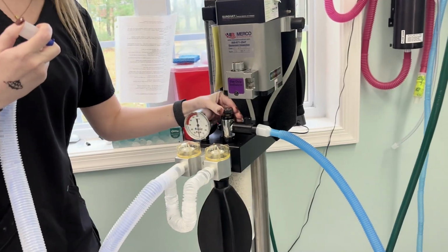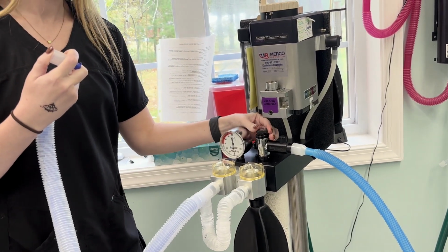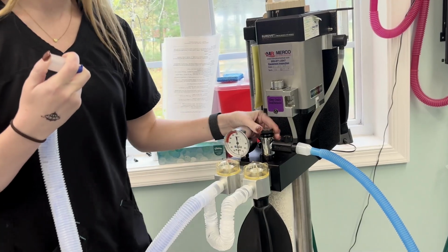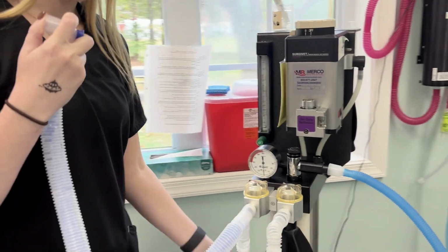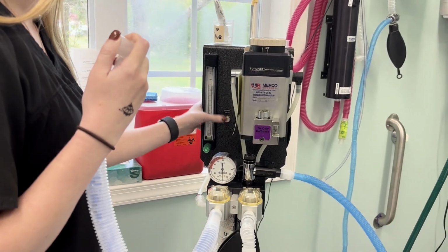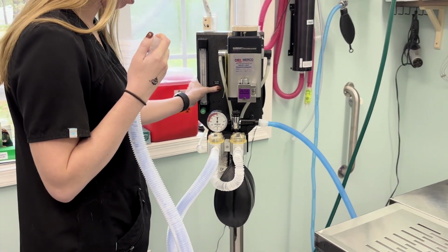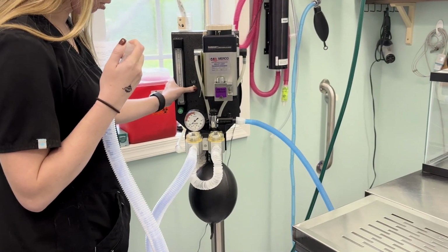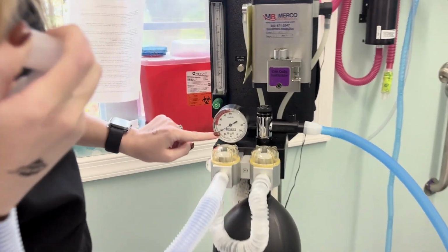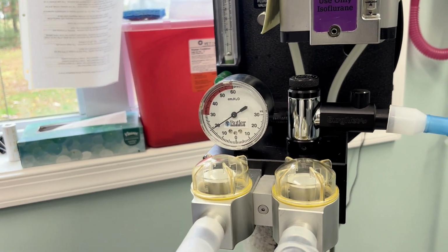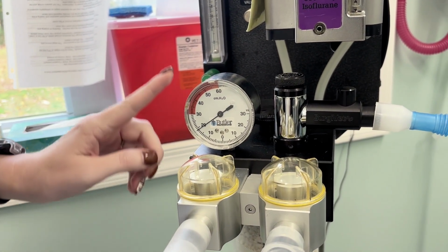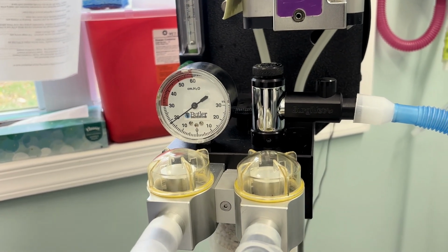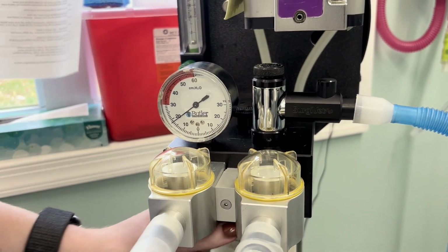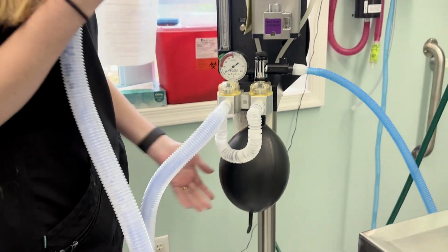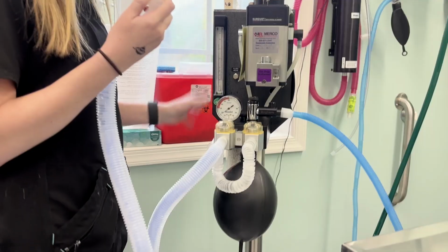Next, I'm going to use the pop-off valve, and I'm going to close that. So I'll turn that all the way till it stops. And then I'm going to use my flush valve to flush oxygen into my reservoir bag. I'll flush it, and now I'm going to do it until it goes up to 20. So now that it's there, you're going to hold it for about 5 seconds, and you want to make sure that it's holding pressure. It can go down a little bit, but if it's really going down, you want to make sure that your bag is on tightly. All these are connected tightly, and everything else is connected tightly.